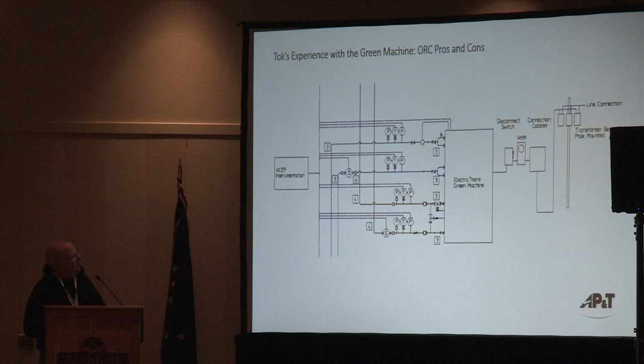As discussed earlier, we did many modifications to bring the plant up to a specification that would support the ORC more effectively. These included increasing the pipe size, installing valves, rerouting everything. One of the changes we made on several different units was the installation of newer, higher capacity heat exchangers. These heat exchangers are on the recovery side, so the engine coolant runs in through one side and out, and the heat recovery system runs through the other side and out.